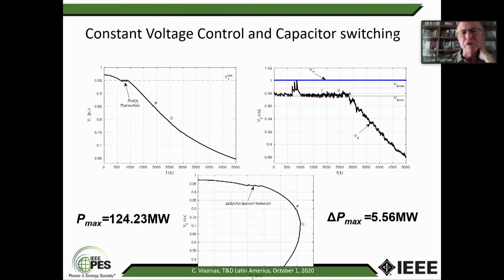Now let's go to use the capacitor switching and also the unity voltage control, so that the wind farm voltage is unity. And you see when the voltage drops, as I said, below 95%, you have the capacitor switching, so the voltage goes back. You see here the secondary voltage that it can go outside the deadband, but then the tap changer will bring it back. Again, we have the variable wind. That's why you see those changes here. And you see here your maximum power is at point C at a higher voltage. And here is your low voltage limit. And you see in the PV, load power versus load voltage, how you have the increase of almost 6 megawatt. And always the comparison, this delta with the one I showed just previously. So you have another 5.5 megawatts on top of the one that you get from the active power.